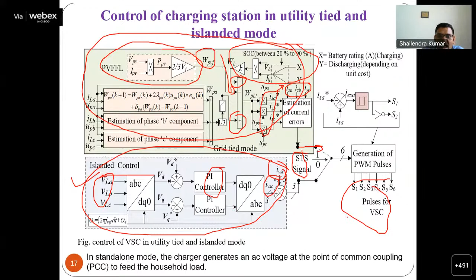On the other side, we have this islanded control. Load voltages are sensed and converted into DQ quantities. These DQ quantities, after comparison, are given to a PI control to regulate the voltages, and finally we generate the VSC reference current, which is compared with the sensed VSC current to generate the switching signal for the voltage source converter in islanded mode.